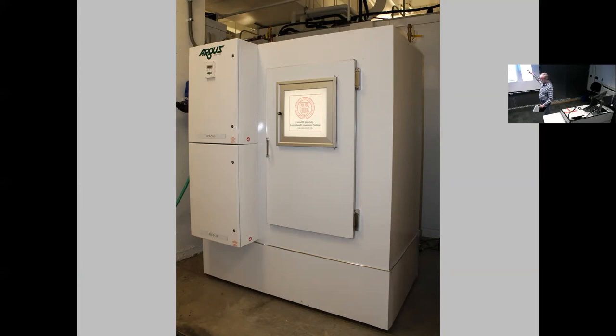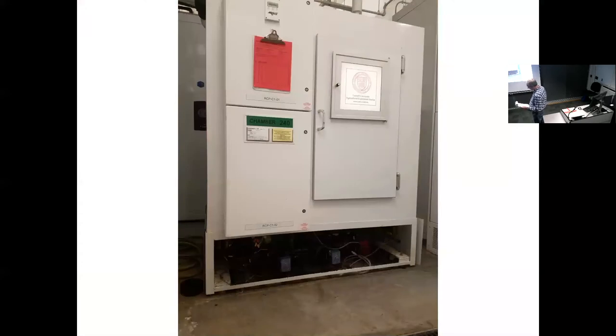And we also didn't put plumbing along the sides in the back of the chamber either. That way, these chambers can be stacked side to side and back to back to maximize the number of them we can fit into a room. Because most chamber rooms that we have around in different buildings are really not big enough. This way, we can really pack them in. So that was the idea there. If repairs are ever needed, we just need to take that panel off and we can get to all the working components. But so far, we haven't had to repair this chamber. It's been more than four years since it was built and it hasn't stopped working yet. And I've replaced the light bulbs once. It's hard to avoid doing that. But that's been it. And this chamber is very energy efficient. We took the basic concept of the Percival design using the chilled water and the building reheat water to regulate the temperature and we improved it a little. And here's how we did it.